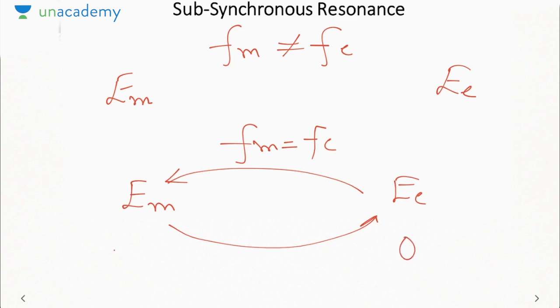So at some point it will so happen that the energy in the mechanical domain will be Em plus Ee, and the energy in the electrical domain is 0. Now due to the increase in mechanical energy or mechanical power, the torque produced in the machine will also be high. Those high torsional torques or torsional frequencies can cause damage to the rotor of the machine. This is the most dangerous impact of series compensation, that the rotor of the machine may get damaged due to high torques produced by high energy in the mechanical domain. That is called subsynchronous resonance. Subsynchronous resonance implies resonance at a frequency less than the synchronous frequency.